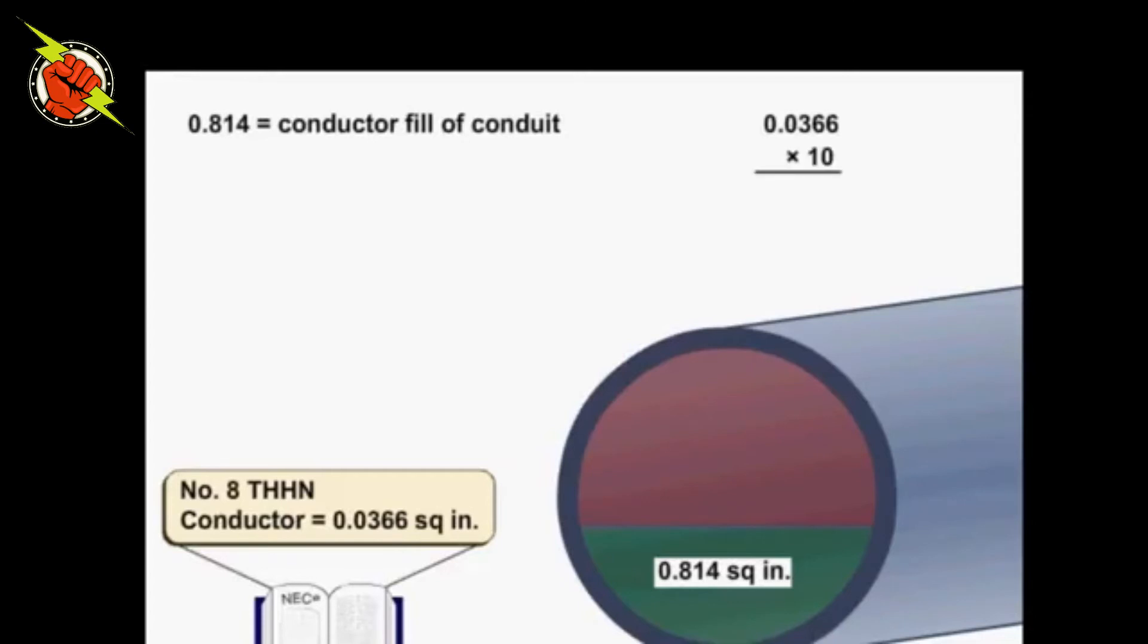If 10 number 8 THHN conductors are in a conduit, then the cross-sectional area of the existing conductors equals 0.366 square inches.